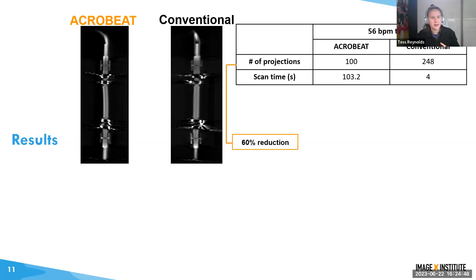If we look at some of the stats up in this right-hand corner, the number of projections is a surrogate for our X-ray dose. So with acrobeat, we've more than halved the amount of dose that a patient might receive. Now, the scan time is very long, which is to do with that slow gantry rotation, so we can definitely look to bring that down in the future. It even shows that within that 4 seconds, you're getting a lot of motion that could potentially be quite damaging to your clinical decision making. So yes, there's a 60% reduction.